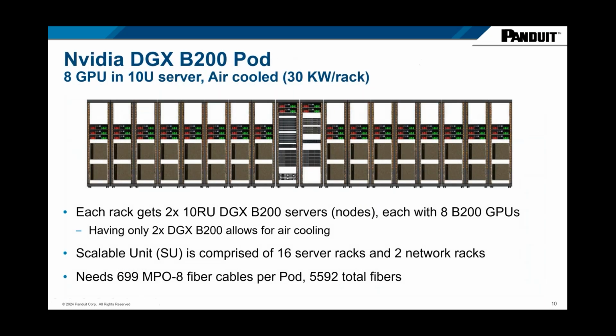So just a quick look - this is an example of what an Nvidia large cabinet pod looks like, just showing this as an example. This can actually be air cooled because they're only putting two of the chassis in there, two 10RU chassis, with the network switches in the middle. This nets out to about 30 kW per rack, which can be done in more of a traditional common space or environment.